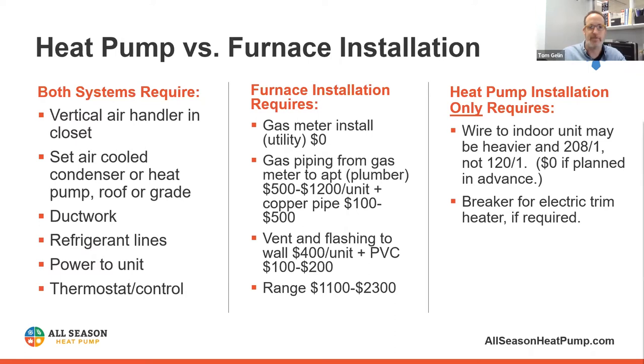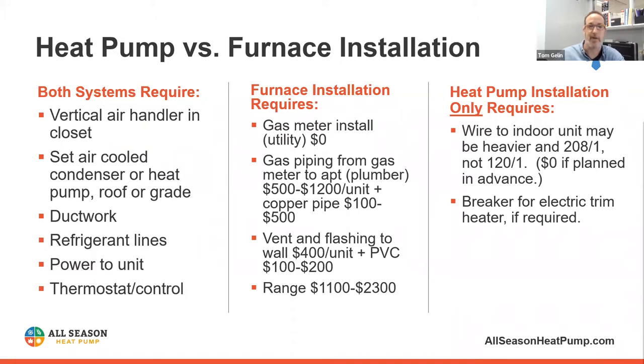For the HVAC contractor, when we have a furnace we have to run a vent. Assuming sidewall vents — typical for multi-story multi-family — it's a two-trip job: one to land the flashing at the wall, another to get the PVC pipe over there. That's about $400 in labor. Then you have to buy PVC and get a termination. When you put those two pieces together — forget the meter — you're over a thousand dollars, sometimes in excess of $2,000.